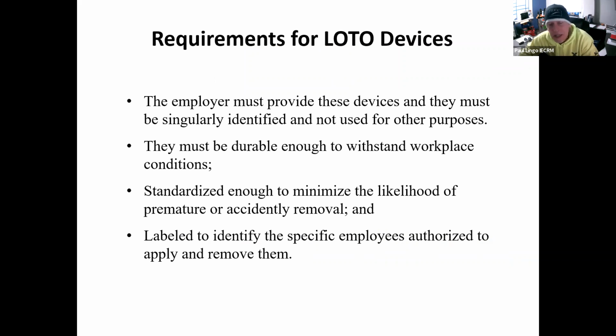They need to be secured in a way that you can't just remove, like tape. I can just remove a piece of tape, so you need it secure enough that it can't be easily removed, because someone will try to get that circuit on. I've been on job sites where I had to disconnect my entire turtle because there was a problem with people trying to get into it. So make sure you're locking stuff out in a way that people know it should be turned off. Don't use a piece of tape, use the lockout tag out engineering control, and make sure it's labeled: what is it doing, where's it coming from, who's responsible for that tag?